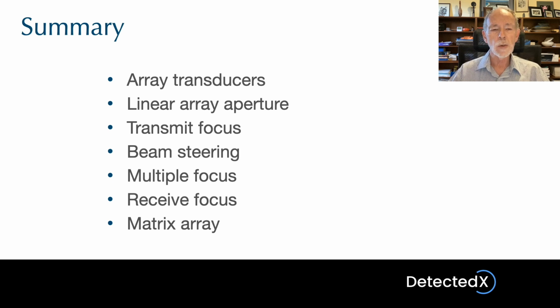I've just discussed the way when the machine is transmitting, it can use delays to create a focused beam. It can also use those same delays to steer the beam in different directions. I then discussed the fact that an extension of this idea is the use of multiple focuses, which can be useful in some situations, particularly when you're scanning quite superficially, to improve the uniformity of the focusing. The cost of this, though, is that the frame rate of the image is reduced because the image is actually formed of multiple strips, each with a different focus.